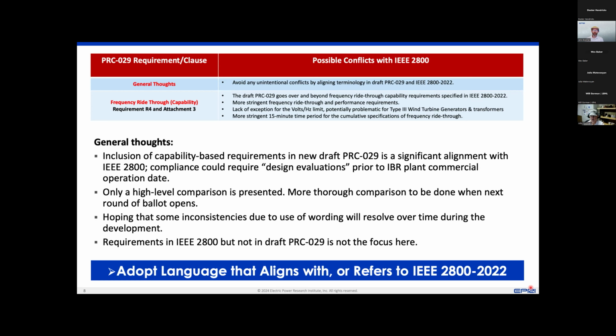So the question that comes up is, does a NERC reliability standard have to adopt the most stringent frequency ride-through requirement, or could selected regions go above and beyond a NERC requirement? Also, we identified a lack of exceptions for the volts per hertz limit. Potentially, that could be a problem for type 3 wind turbine generators and transformers. This is where some of the details considered in IEEE 2800 could matter, and we encourage the standard drafting team to further consider some of those matters. And last, we identified a more stringent 15-minute time period for the cumulative specification of frequency ride-through.